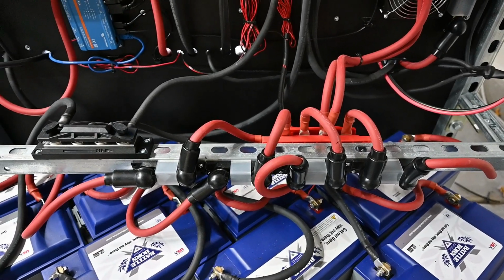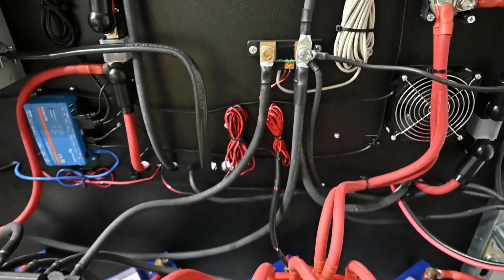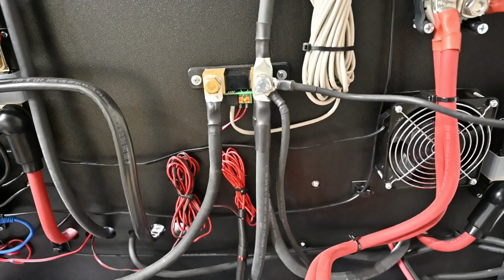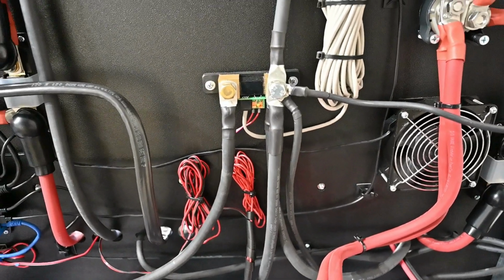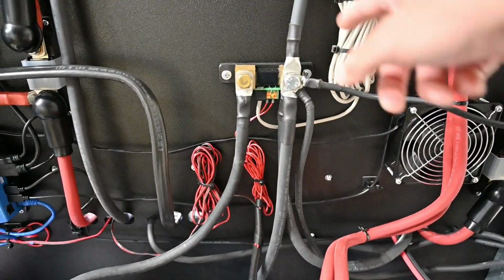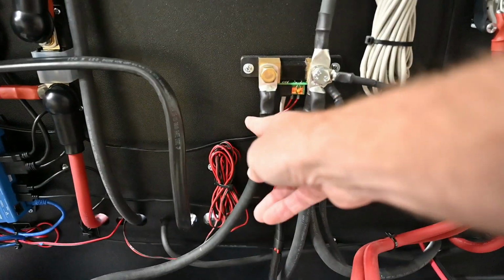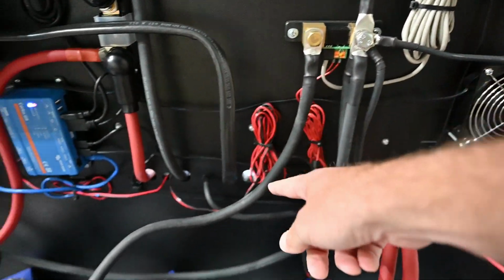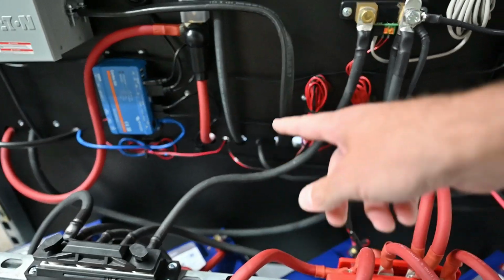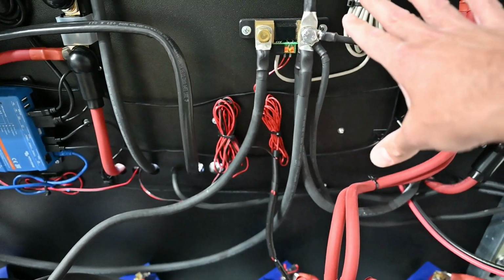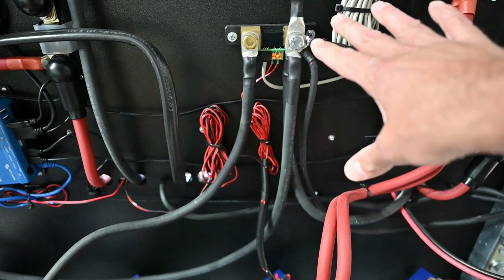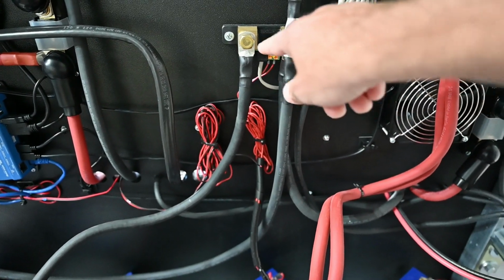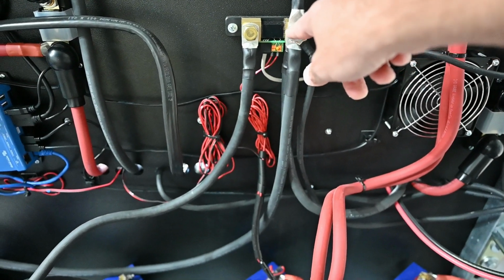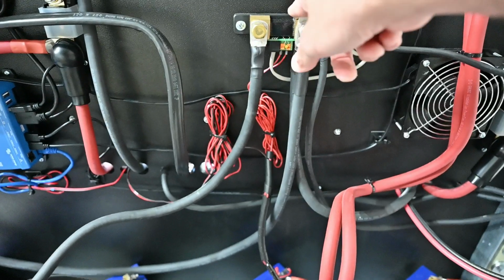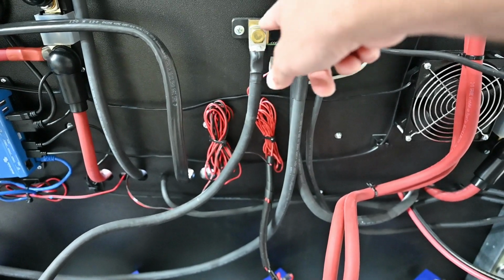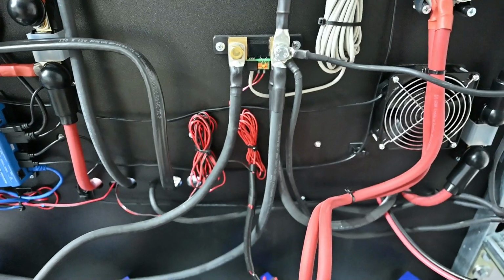So what exactly is going on in terms of the monitoring? It's achieved by a shunt. There's a single terminal on one side that goes to your battery bank, and everything else is connected to the other side of this shunt. This is a very low resistance path, and it can monitor how much current is flowing throughout the system at any given time.